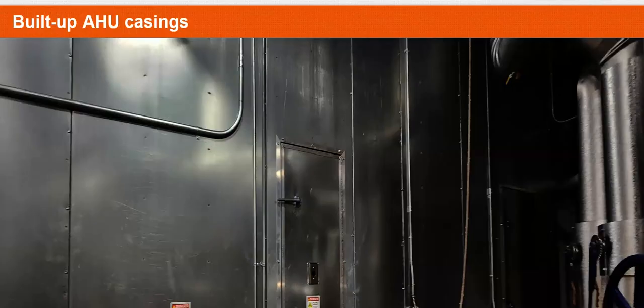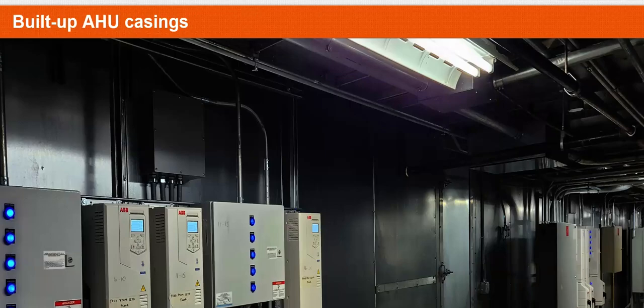Then you're going to have to look at the structural as well as possibly a thermally broken construction, depending on the parameters that you have. This is how they look like. As you could imagine, there is not such a thing as zero fasteners when you're getting to this size. Eventually, you're going to have to support it. So if you see manufacturers out there saying, hey, this is self-supporting and this 80-foot wide by 40-foot tall plenum is just going to fly alone in the air, it's not such a thing. You're going to have to, at some point, support them properly.